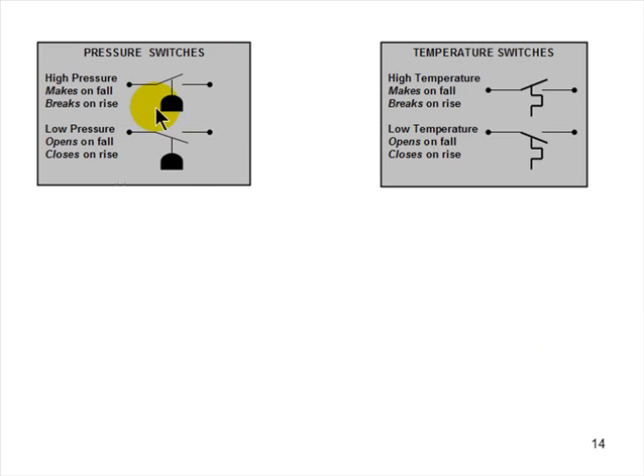Other switches. You look at this, you should know that's a pressure switch. Looks like a bell, right? And the pressure is always from the bottom. Now, this switch is above the line, so it's a high pressure switch. This switch is below the line, so it's a low pressure switch. What's the action of this switch? It's going to open on a rise and make on a fall. This switch is going to open or break on a fall in pressure and make on a rise. High pressure, low pressure. You know what happens.